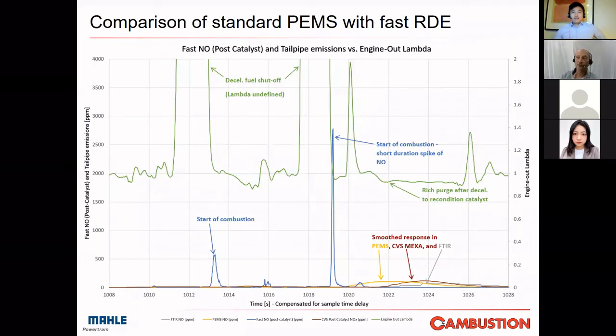So yes, that's a very good question, because this equipment cannot be used as a substitute for PEMS. The NOx system's specifications are within range, but the PEMS system has to contain a variety of analyzers, so you put your PEMS system on and you will be able to measure NO, NO2, CO, CO2 and hydrocarbons, for example. If we put our CO analyzer on here, the drift of our CO analyzer is 1,000 times faster, but 10 times more drifty than a PEMS piece of equipment. So from that basis, you would not be able to use our equipment for legislative certification purposes. And that's not what it's designed for.